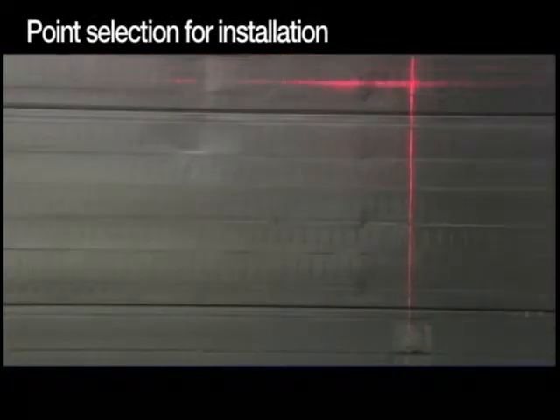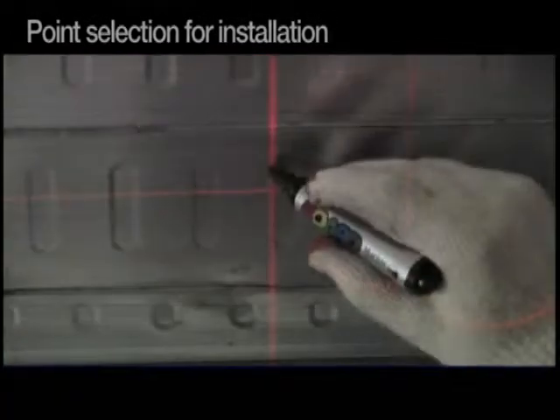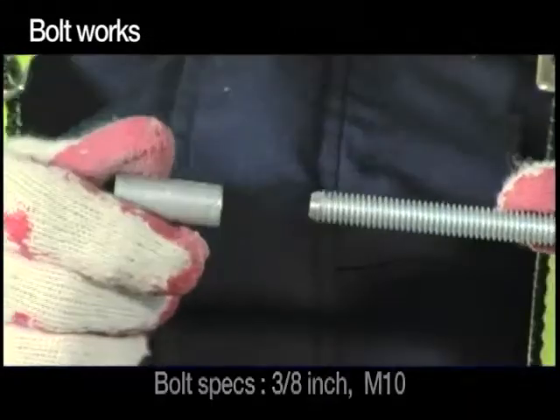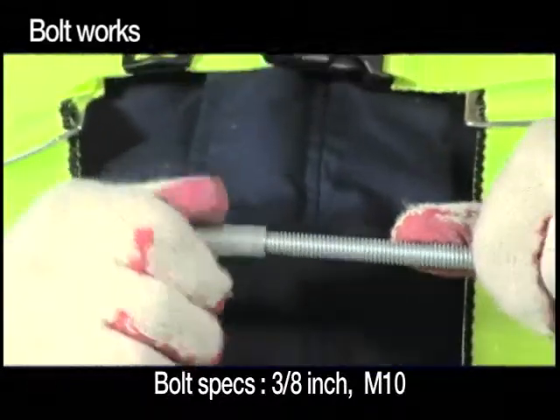Using an indoor unit's pattern sheet, select a good location on the ceiling and mark it accurately. After that, using an electric drill, punch some holes and adjust the length of your bolts in accordance with the installation height and fix it to the ceiling.